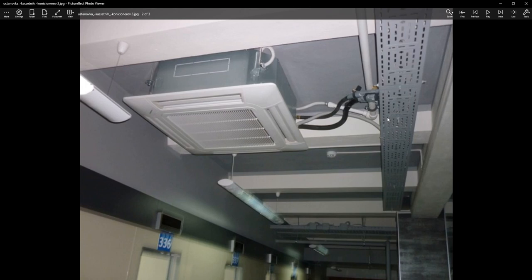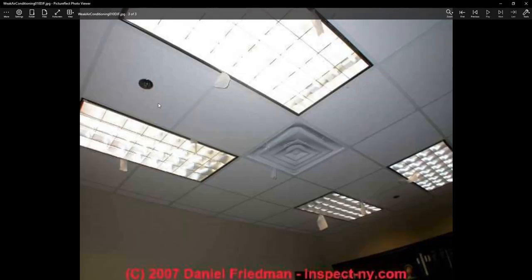Another example: if you have air ducts, the luminaires may be suspended or surface mounted on an extra ceiling below the original ceiling. In this case, we should add this extra layer of ceiling. There could be HVAC ducts above this ceiling, so the distance from the luminaires to the ground is less than the distance from the ground to the original ceiling.